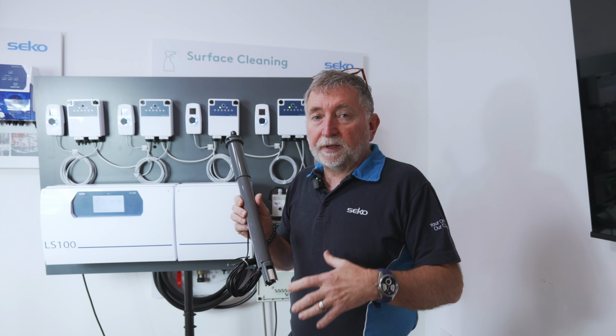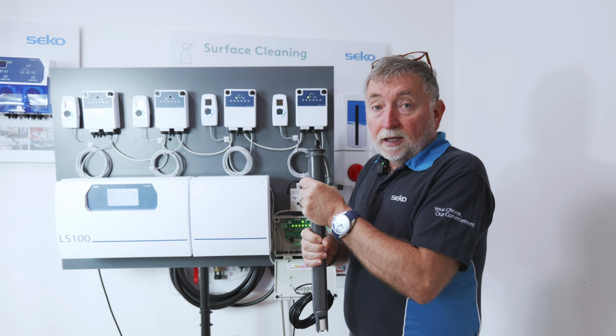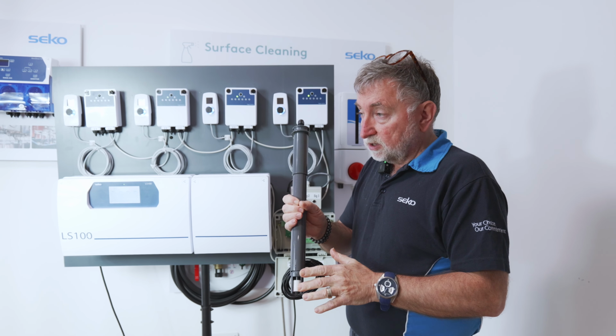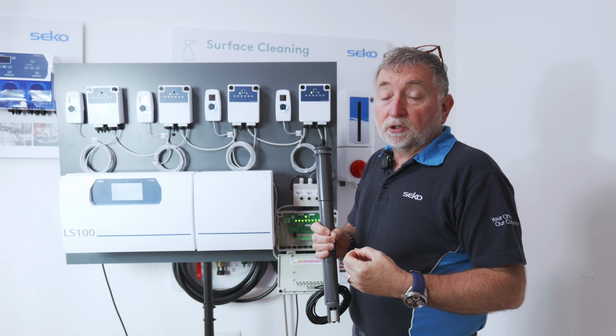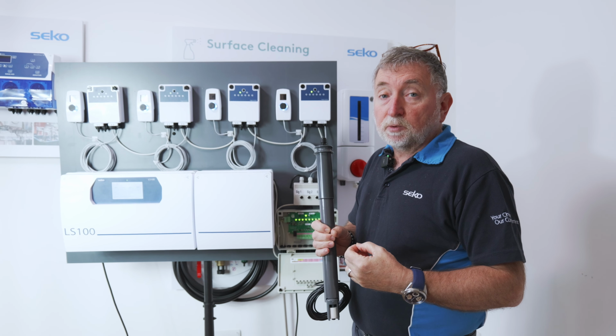Traditionally, the only way you would be notified if you're running out of chemical is to use a suction device with a low-level float, which actually drops when the chemical reaches a certain level, and when connected to a low-level alarm module will indicate that you're running out of chemical. Now, these work very well, but obviously it is additional cost to have the level module and the suction devices with the floats. So another useful function on the LS100 is a depletion alarm.